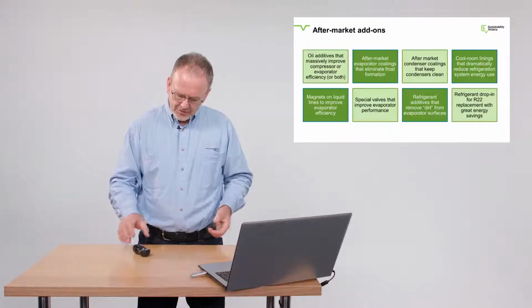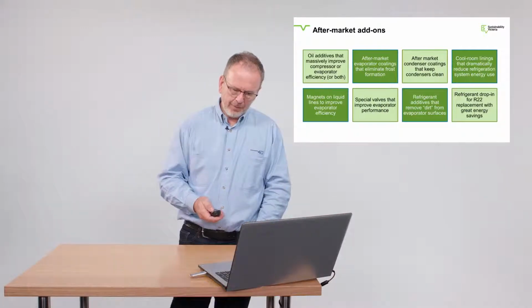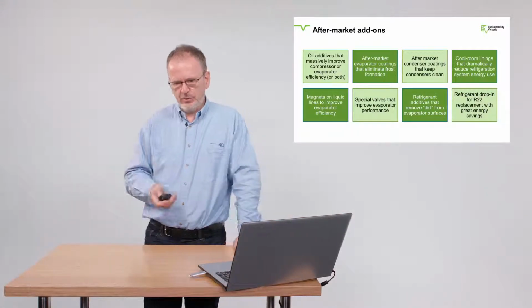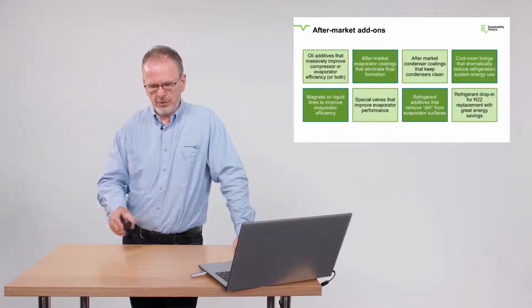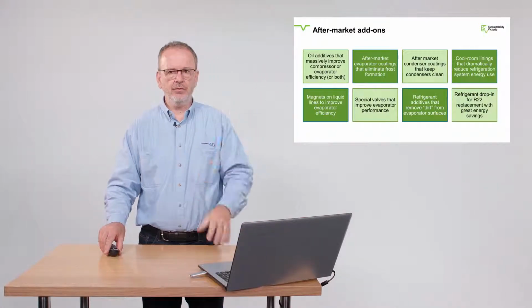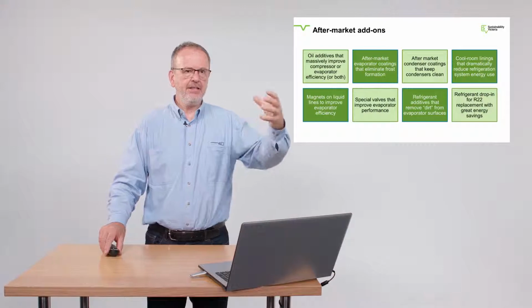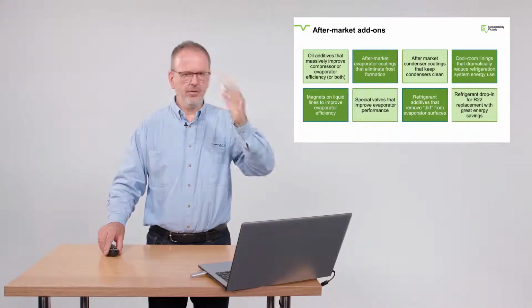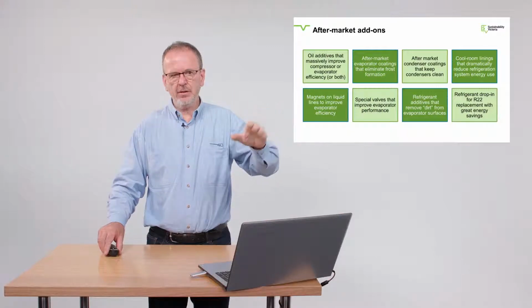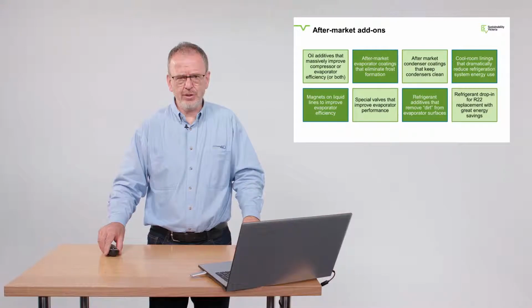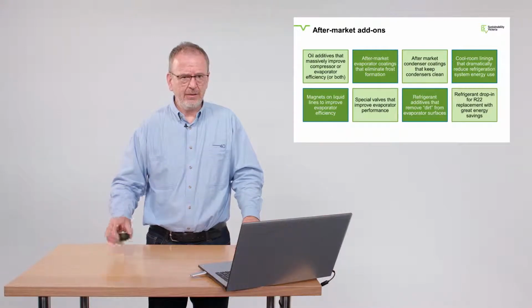So there are all these systems out there, and we've recently had a spate of systems which use solar energy to boost the efficiency of the refrigeration system by heating the gas after it comes out of the compressor. So the thermodynamics makes no sense, but these systems are being sold, and unfortunately I've seen one or two IGAs also buy that.